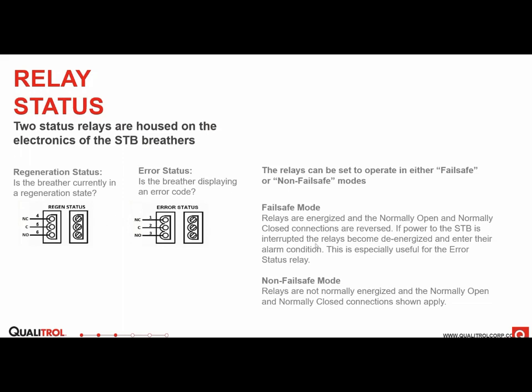And both of these relays can be configured for fail-safe mode. This is really useful because you can put the error status in a fail-safe. So when it's powered on, your normally closed and normally open swap, and then that can be used as a power status relay. If the breather ever loses power, it'll close on that normally open, and then you'll get an alarm for that if there's ever, for any reason, that you lose substation power.